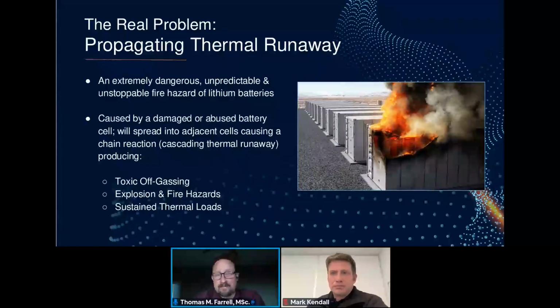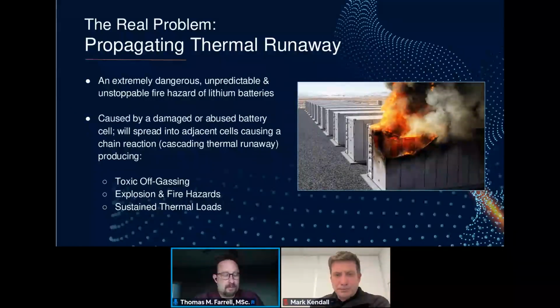There are a lot of causes for these. It can be a single cell that begins to fail because it's damaged or because of a manufacturing flaw that creates an internal short, causing it to go into thermal runaway. That can cause an electrical short to cells electrically connected in parallel, as well as thermal conductivity failures in adjacent cells, which keeps causing a chain reaction. Obviously, the heat generated by these, either from flame or just the exhaust gases coming off of them, can cause additional cells to go into thermal runaway as well.